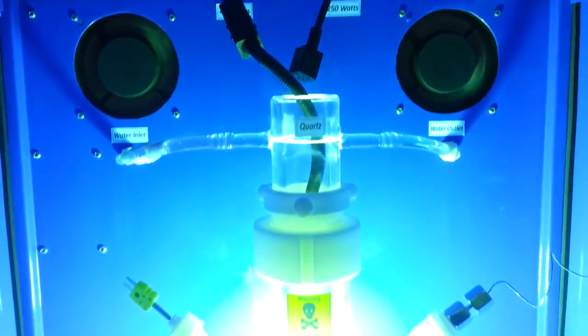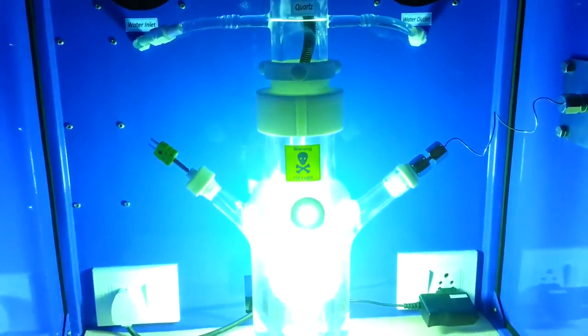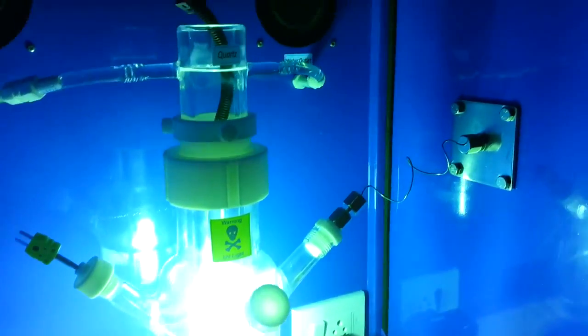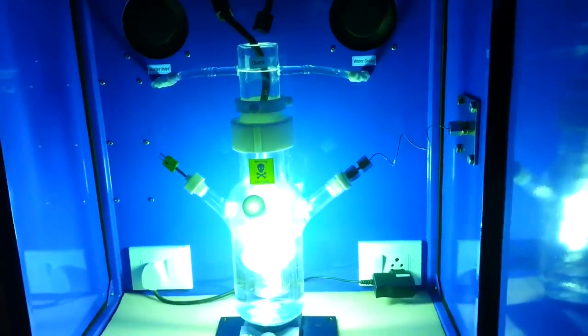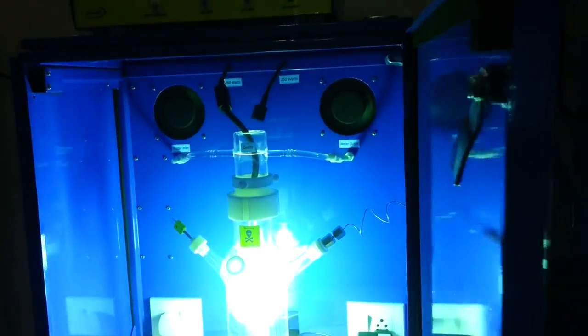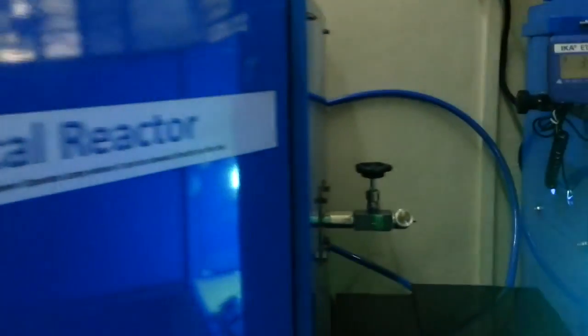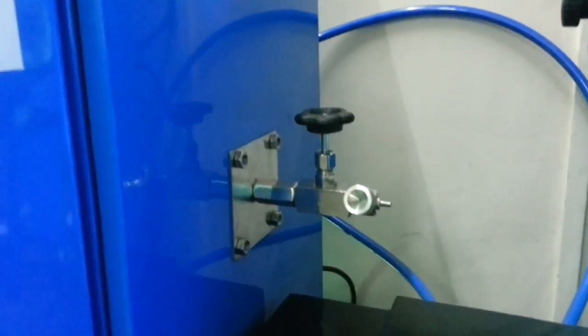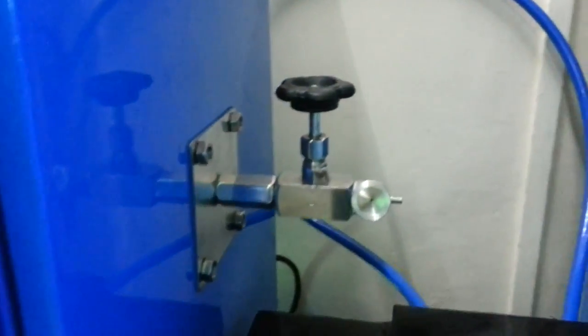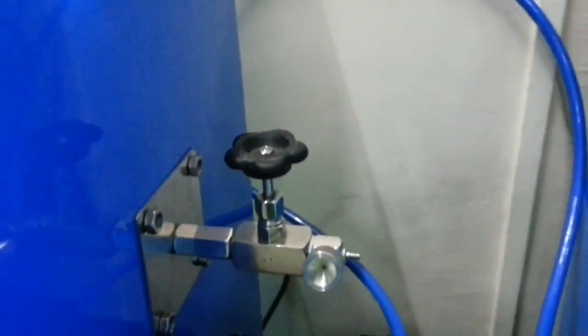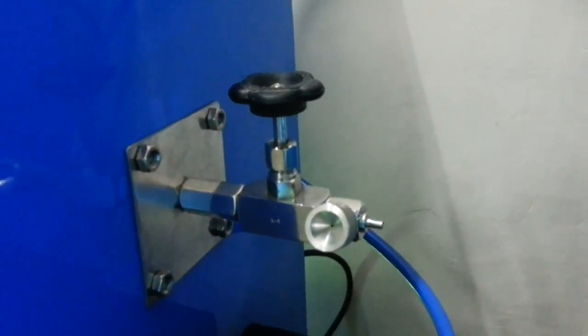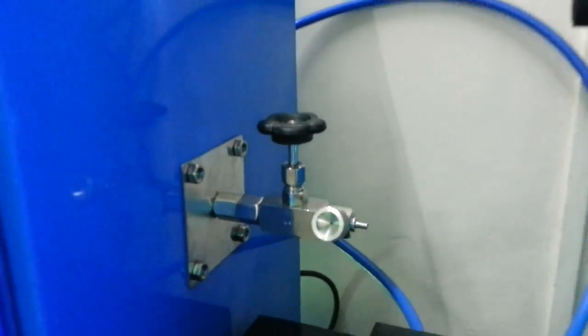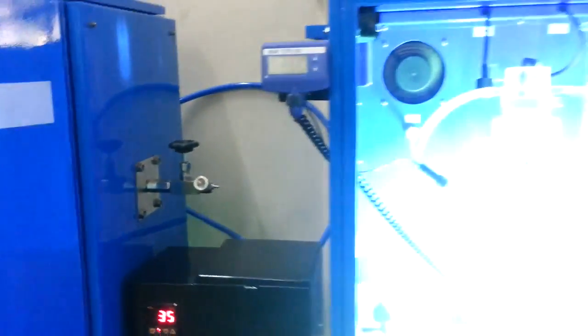Dual exhaust system, special hydrogen port. The unique feature of this unit is even when the system is closed, you have an external valve and a septum for hypodermic syringe to collect gas. You have an optional connector Swagelok to GC in order to avoid any leakage of hydrogen gas.